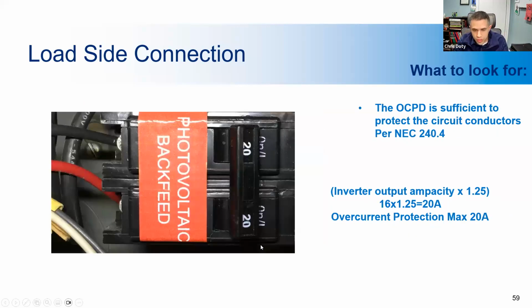All right, so the overcurrent protection device must also be properly sized. Same rule, 125% of the output ampacity. This is vital to a safe, code-compliant system.